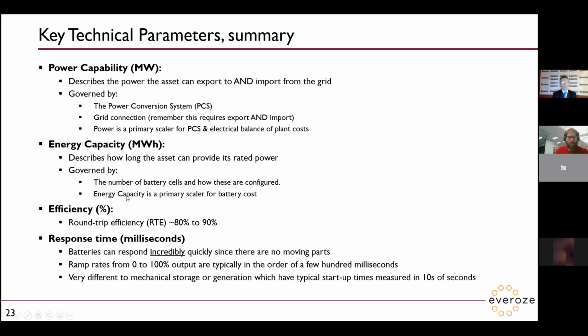Energy capacity is more a function of what revenue streams you're wanting to access. If you want to do a lot of trading, you might go for more energy, a longer duration battery, more megawatt hours, so you can discharge over a longer peak price period, or charge over a longer negative price period. Whereas for frequency response, you just want to get your power out quickly, because usually the events are quite short-lived. Dynamic containment requires only 15 minutes at rate of power, which is pretty short.